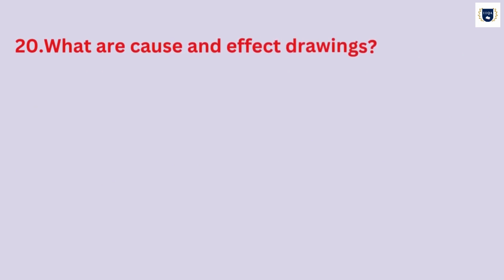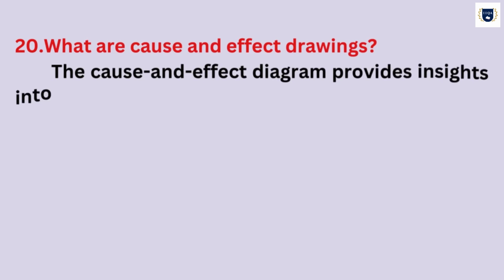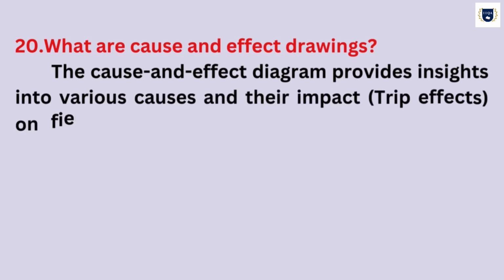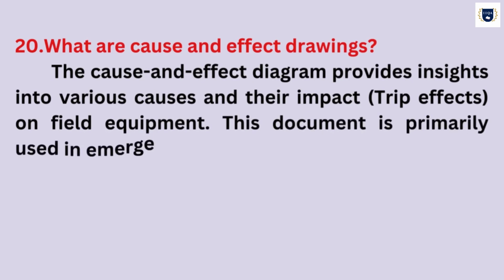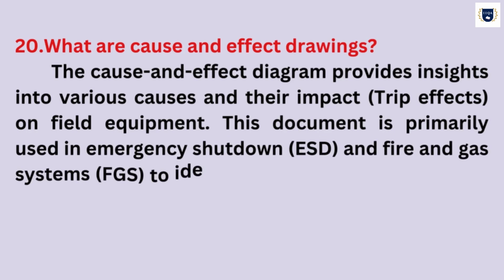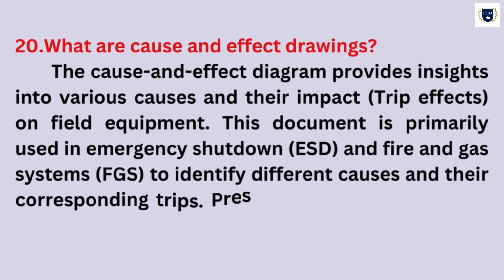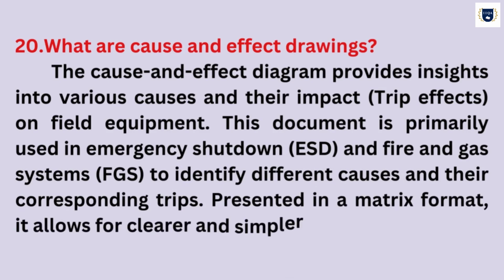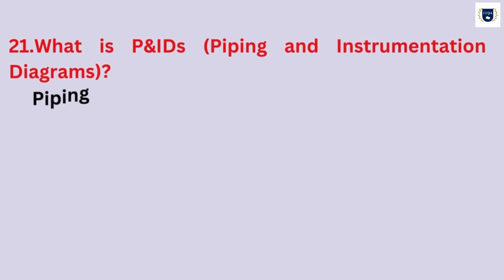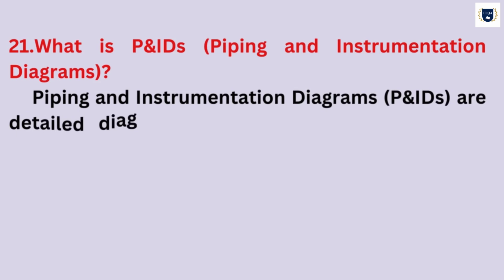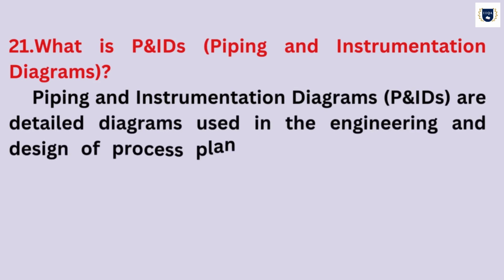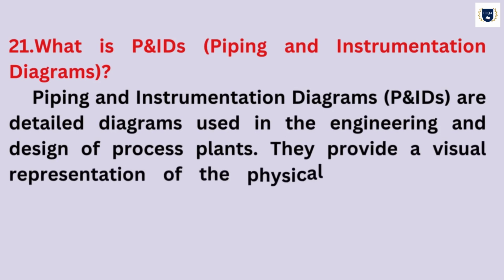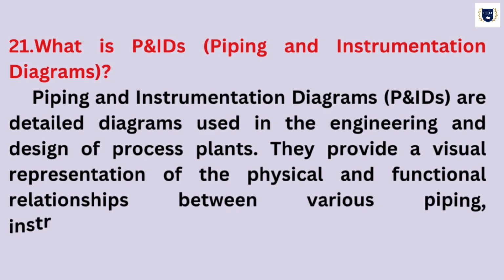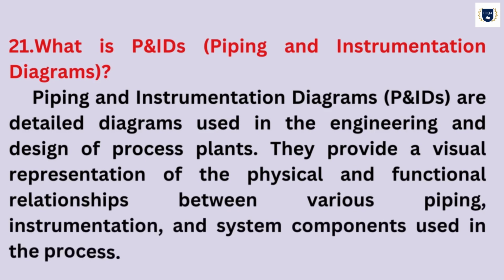What are cause and effect drawings? The cause and effect diagram provides insights into various causes and their impact, trip effects, on field equipment. This document is primarily used in emergency shutdown and fire and gas systems to identify different causes and their corresponding trips. Presented in a matrix format, it allows for clearer and simpler interpretation. What is P&ID, Piping and Instrumentation Diagram? A Piping and Instrumentation Diagram is a detailed diagram used in the engineering and design of process plants. They provide a visual representation of the physical and functional relationships between various piping, instrumentation, and system components used in the process.